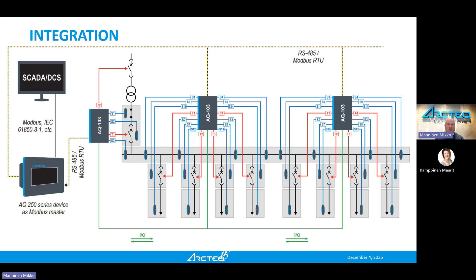This one is from a substation, a 110 kilovolt substation. It is a single line drawing scanned from the PDF, and it has just been configured inside the relay. This is very easy and it is actually a very flexible display. One of the best parts of using this kind of display and alarm annunciator or relay is that you can actually know what occurred, when, and where.